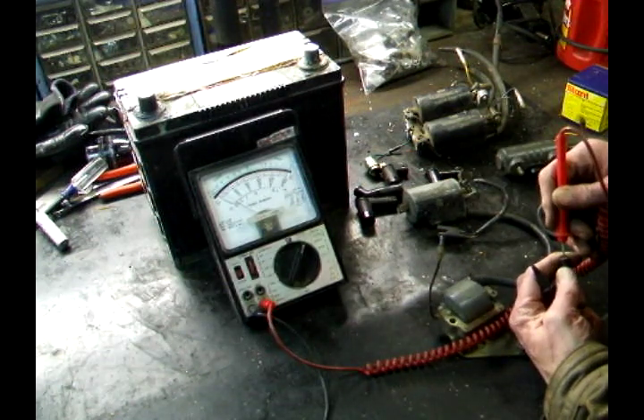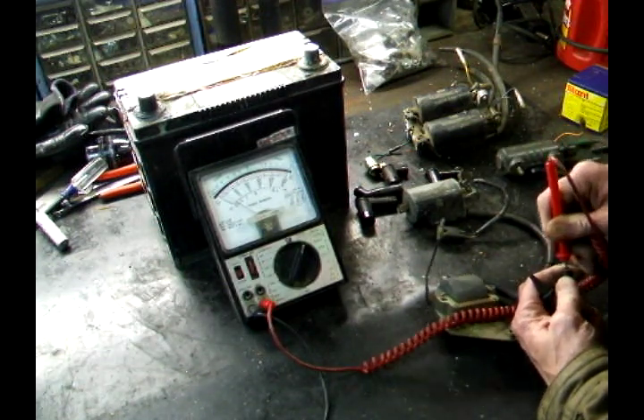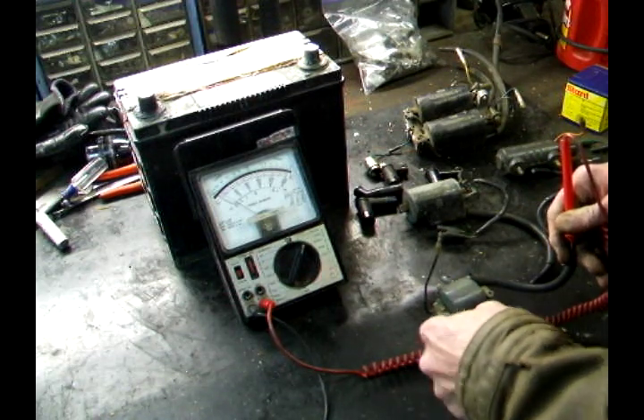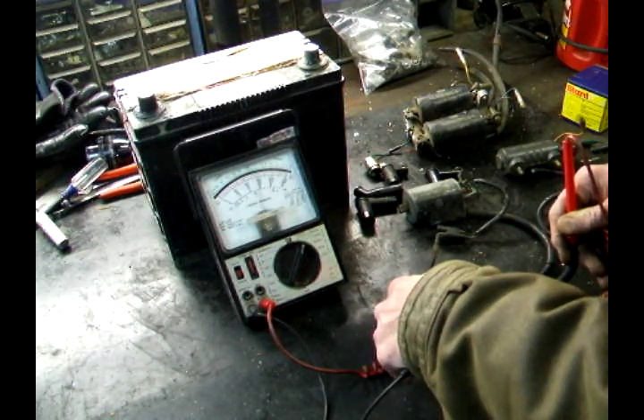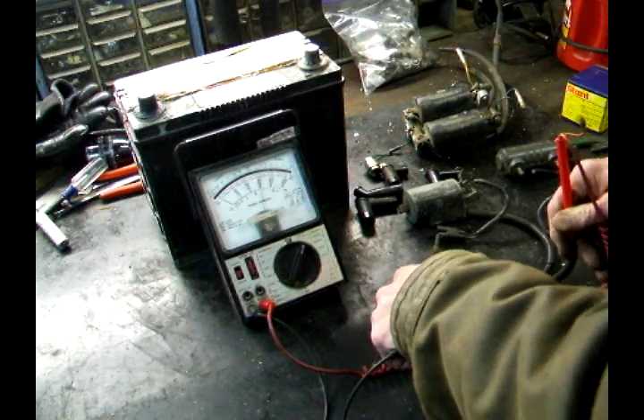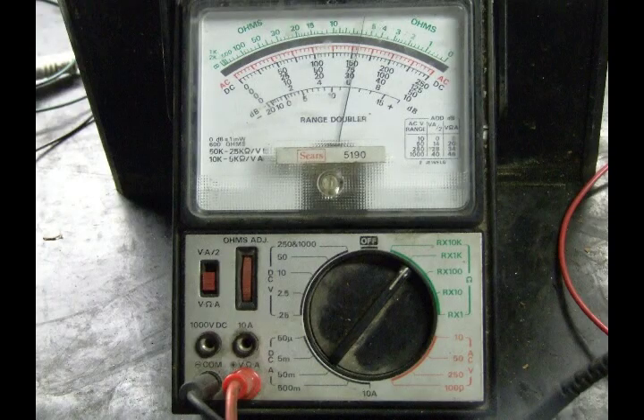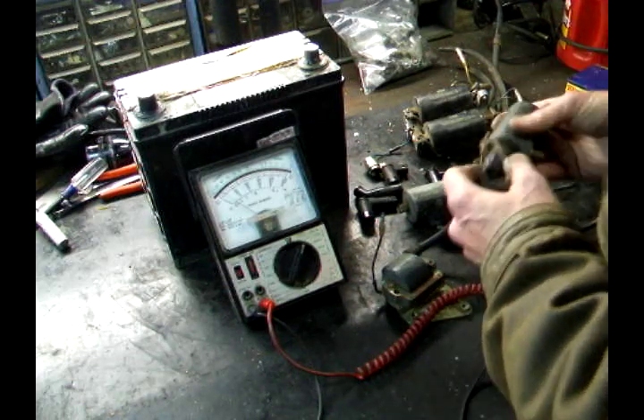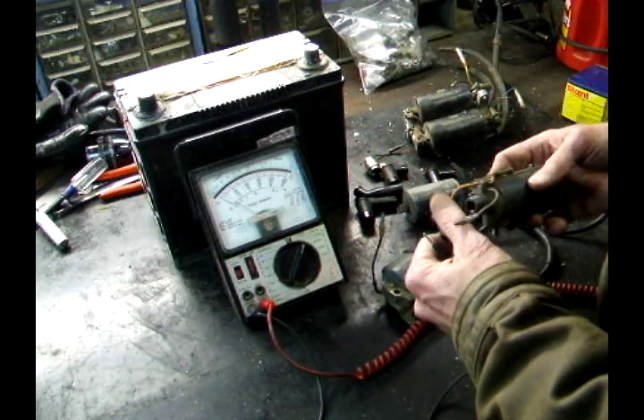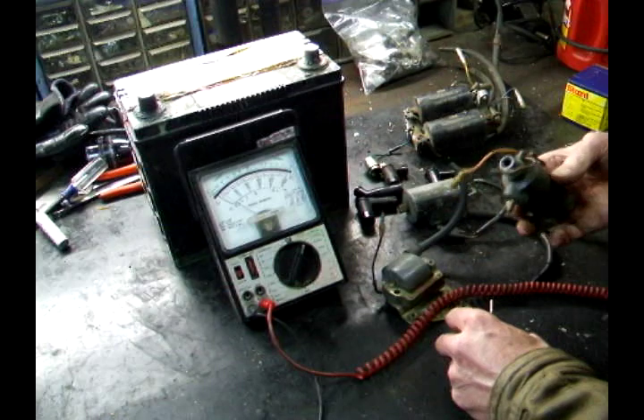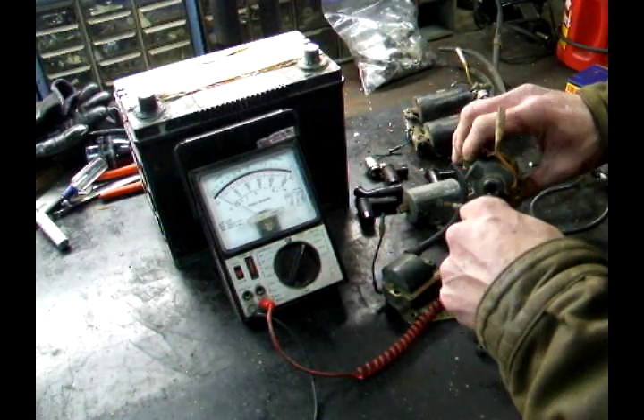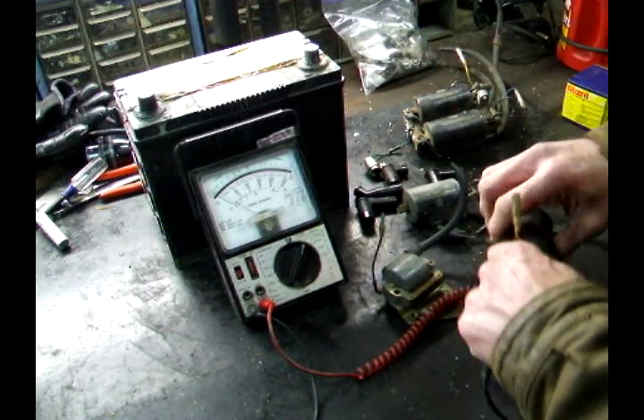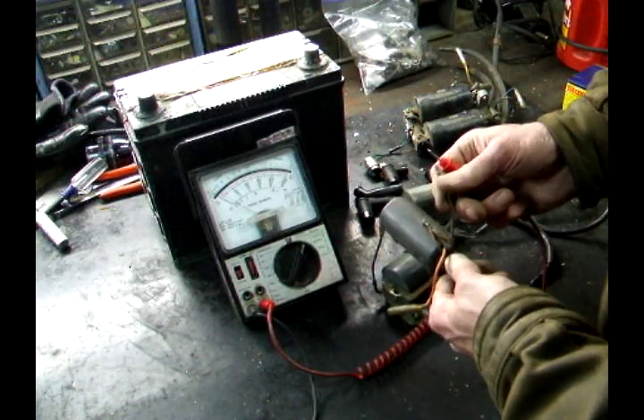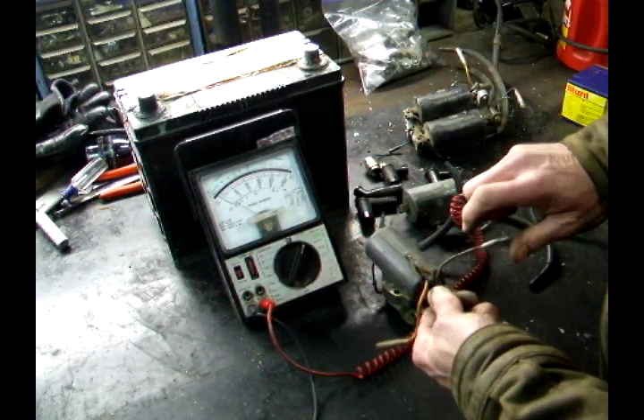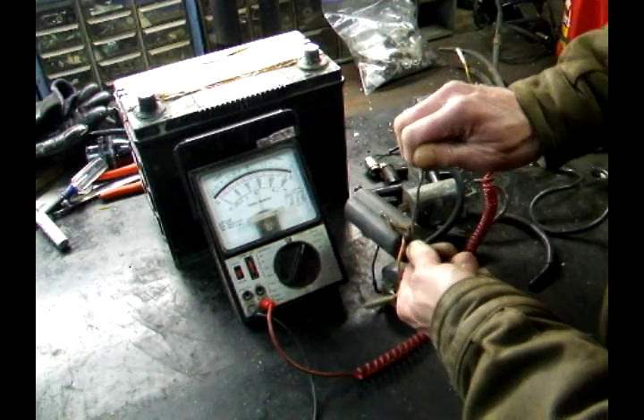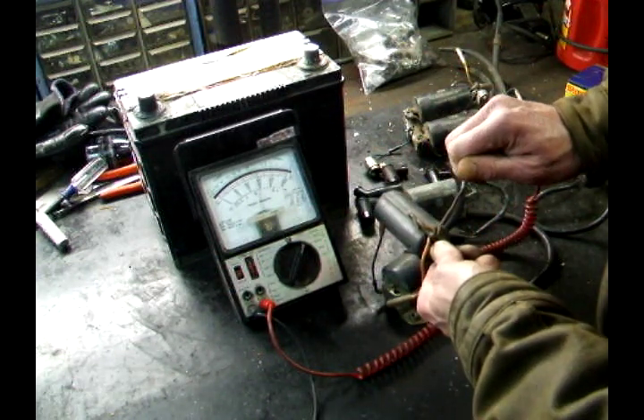Poke your red lead into the end where you can see the wire. Ground the other part out. And this one's about 6,000 ohms. If it's, say, this style, you'll need to remove the end. Inside there is a barb. Touch the brown wire or the one that's not coated. You'll see on the reading that this one's about 8,000 ohms.